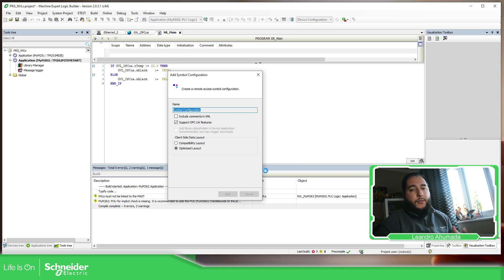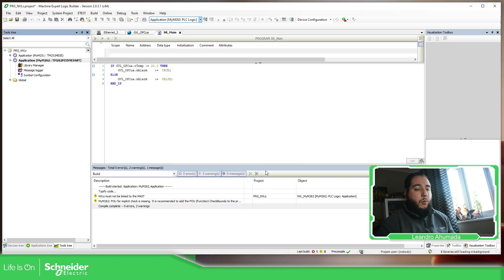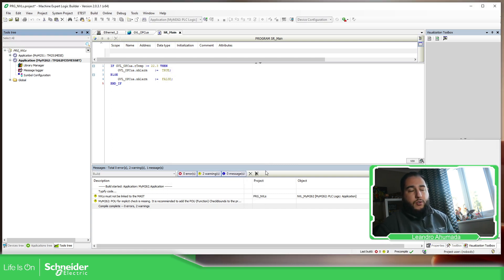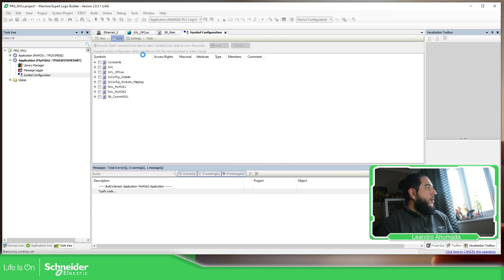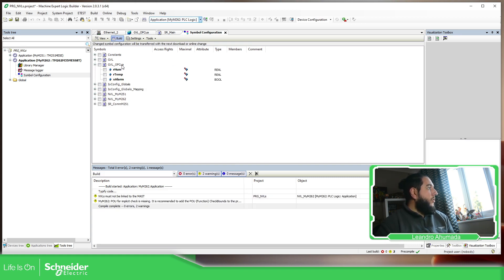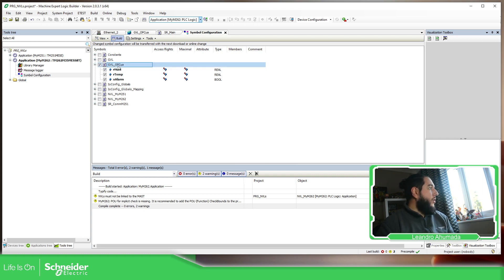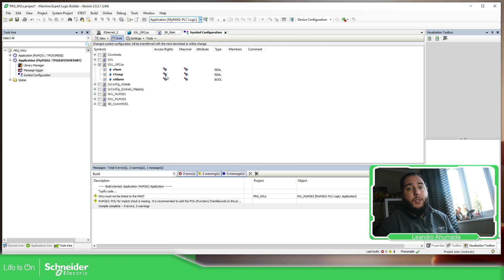As soon as we add this symbol configuration with the OPC UA functionalities, we should be able to see the GVLs or POUs that we have in our application. So as you can see here, the OPC UA GVL that I created, I'm going to select all of these variables. And here you have the access right. So here you can define if the variable is going to be read, write, or read-write.